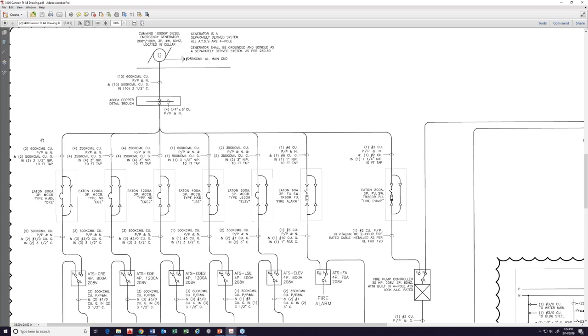what the code is. And the code does require separation between the different loads. So for example, if I'm feeding emergency loads versus legally required or versus optional standby loads, they have to be separated. So if there's a problem with this 800 amp circuit breaker, it will not compromise any of the other circuit breakers. And this is how I design it. So I am actually saving the customer money, and it is a very reliable system, and it is a very safe system, and it's code compliant.